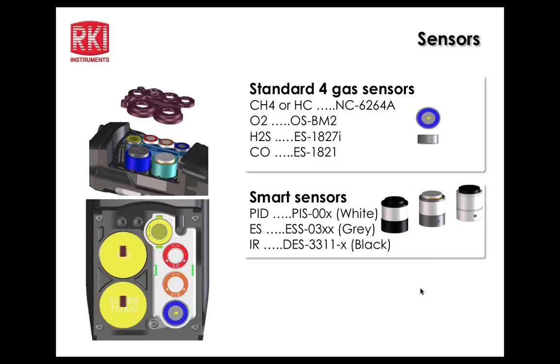If that PID is not in the right slot, will the sensor fail when you turn the unit on? If somebody puts it in the wrong slot? No, it won't. It was originally that way, and we didn't like that it went into fail, so now you can put it in the wrong slot. The only thing that happens is you may lose some sensitivity with heavy, sticky hydrocarbons. So it's optimal to put it in the top slot, but it's not life-threatening if you don't.